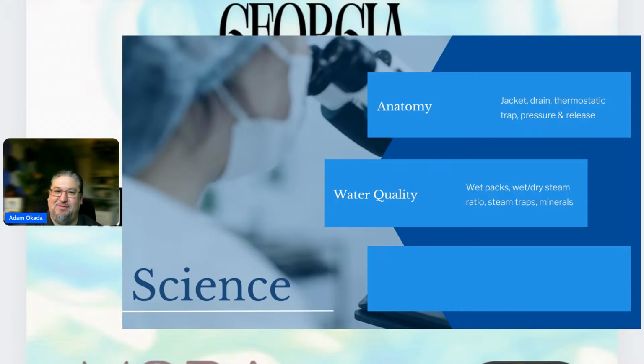It should be 97 to 98% dry saturated steam and 2 to 3% water. Now if you throw that off, like in my department, we had 92 to 93% dry saturated steam and 7 to 8% water. So we were doing an hour of dry time and still coming out with wet packs because there was so much condensation in the chamber that it wasn't able to be cleared out.